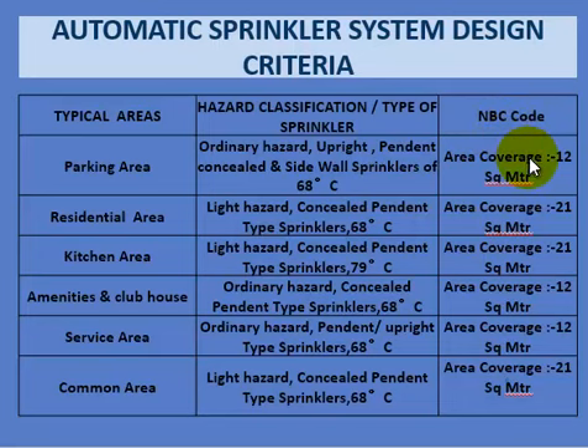The sprinkler spacing for residential areas is 21 square meters, kitchen areas are 21 square meters, service areas are 12 square meters, and common areas 21 square meters, all as per the applicable code references.